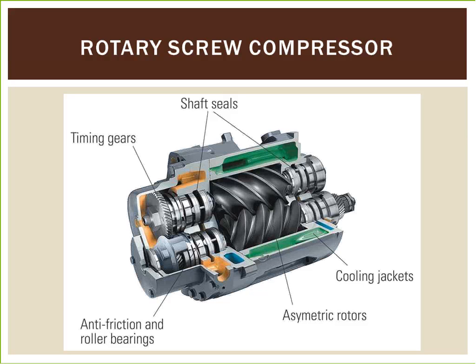The oil-free rotary screw air compressor utilizes specially designed air ends to compress air without oil in the compression chamber, yielding true oil-free air. Oil-free rotary screw air compressors are available air-cooled and water-cooled and provide the same flexibility as oil-flooded rotaries when oil-free air is required.